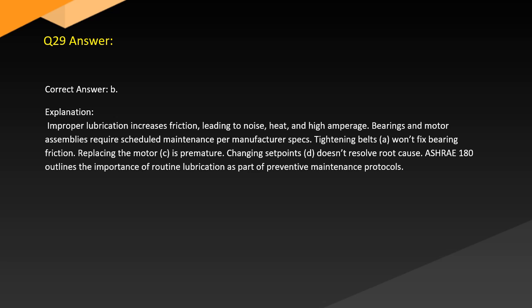Answer. Correct answer: B. Explanation. Improper lubrication increases friction, leading to noise, heat, and high amperage. Bearings and motor assemblies require scheduled maintenance per manufacturer specs. Tightening belts, A, won't fix bearing friction. Replacing the motor, C, is premature. Changing set points, D, doesn't resolve the root cause. ASHRAE 180 outlines the importance of routine lubrication as part of preventive maintenance protocols.